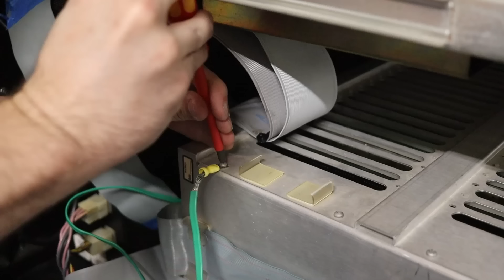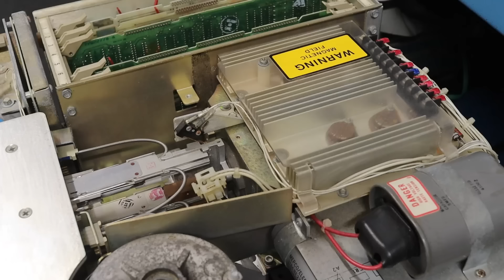DC and AC ground are inherently separated, giving the user the option to tie them together, which I want to do. To achieve that, there's a little grounding strap that goes between the two lugs. I'll install the strap and also connect a big ground cable to the same lug. That cable will route out of the cabinet over to the other cabinet, and I'll bolt it to the card cage. With that taken care of, let's fire this thing up to purge for a bit.